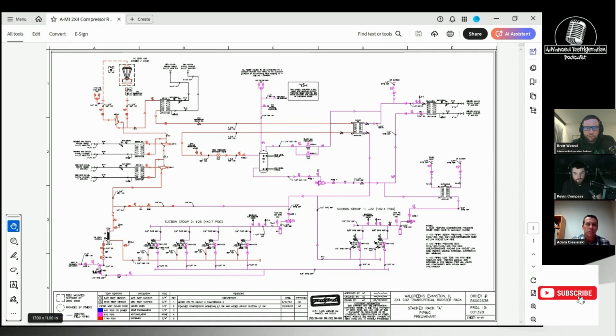The freezer and the coolers are direct expansion CO2. The HVAC cooling in the summer is accomplished by cooling glycol and then circulating the chilled glycol through the loop. And then we also have a secondary heating loop that we utilize in the wintertime, and we produce hot glycol, which then pushes through the air handling units to produce heat in the winter.